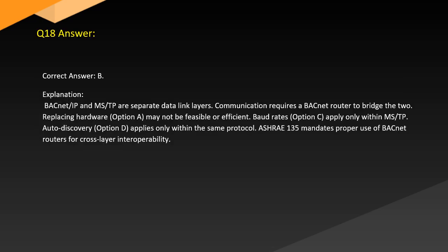Answer. Correct answer: B. Explanation. BACnet and MSTP are separate data link layers. Communication requires a BACnet router to bridge the two. Replacing hardware, option A, may not be feasible or efficient. Baud rates, option C, apply only within MSTP. Auto discovery, option D, applies only within the same protocol.